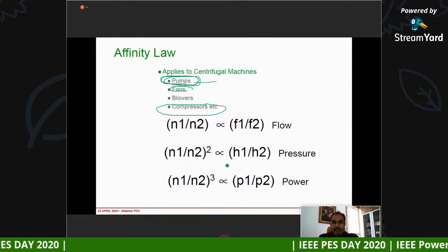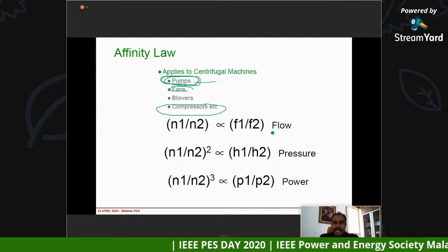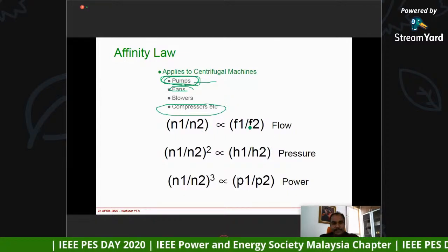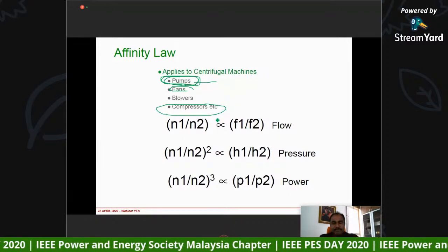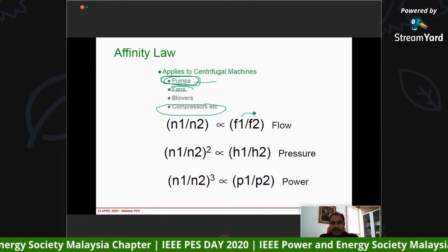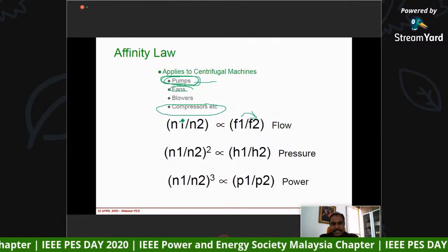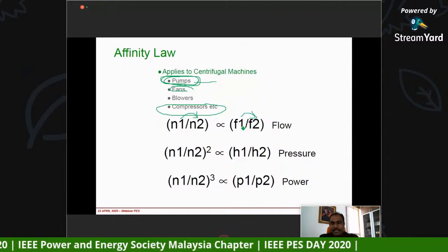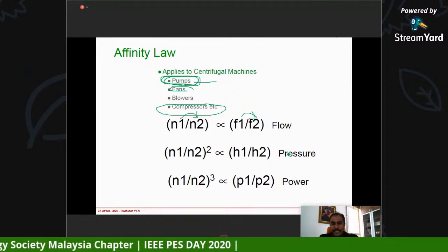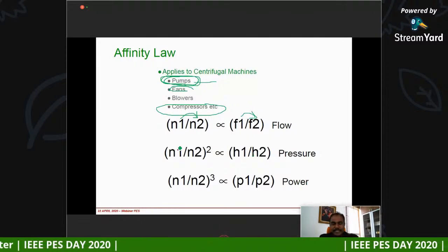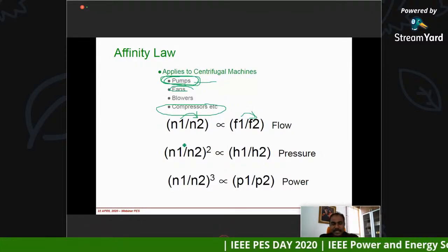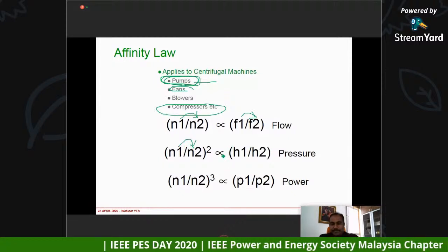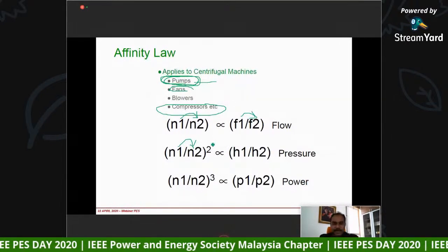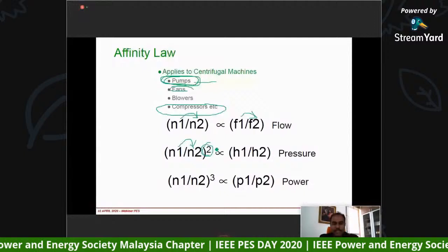And what is the affinity law? As we know, the affinity law says that when there's a reduction of the speed, proportionally your flow is going to be reduced. And similarly, when you have a reduction in the speed, you have a reduction in the pressure with the relationship of square here. Okay, reduction in the speed squared.